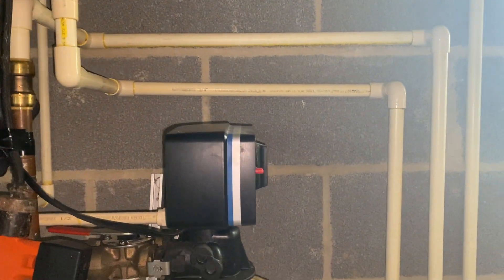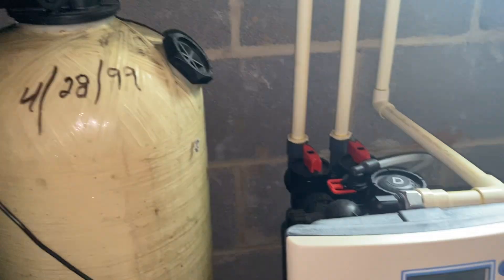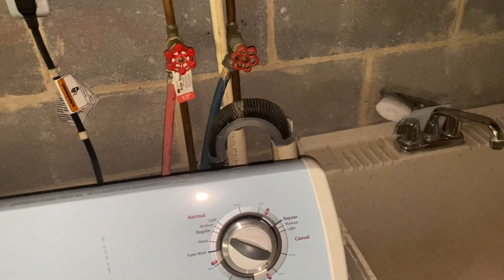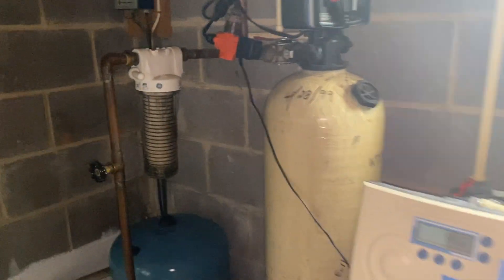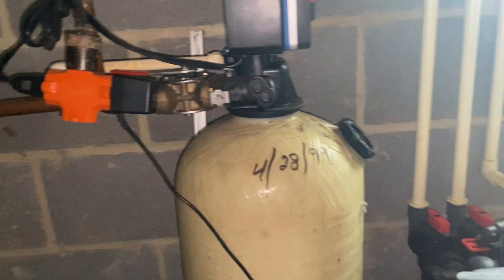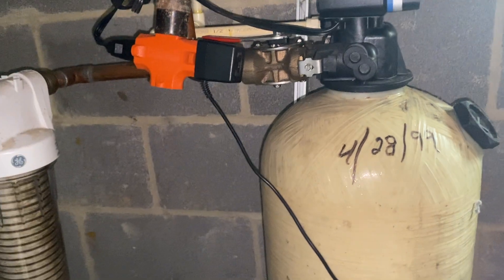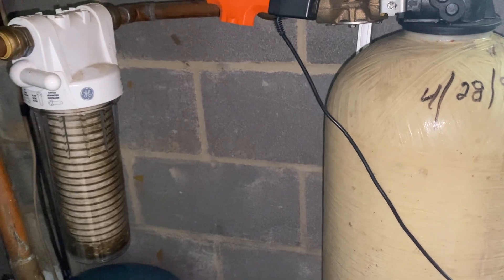In Maryland, you can't do that. The reason it's controversial is the well guys or the plumbers do not want to have to put this discharge line directly into the drain because it's going to create a lot of issues of potential backflow — they're going to have to put backflow prevention and make sure that wastewater from the sewer does not work its way back into the water softener or the neutralizer. The septic guys don't want that stuff going into the septic system because it's going to bring an additional volume of water as well as additional chemicals that can disturb the solids and the chemistry going on inside of your tank.